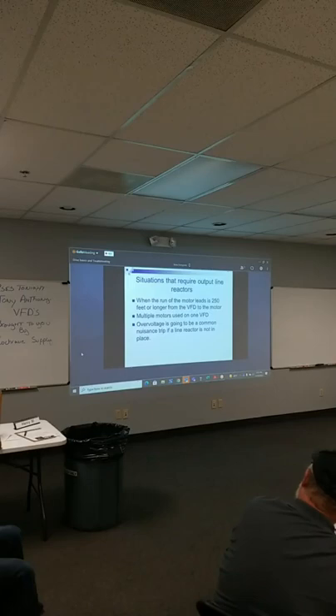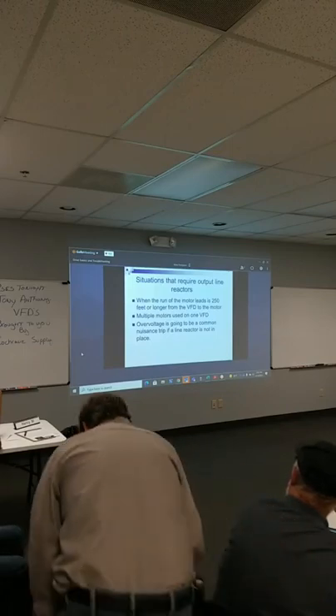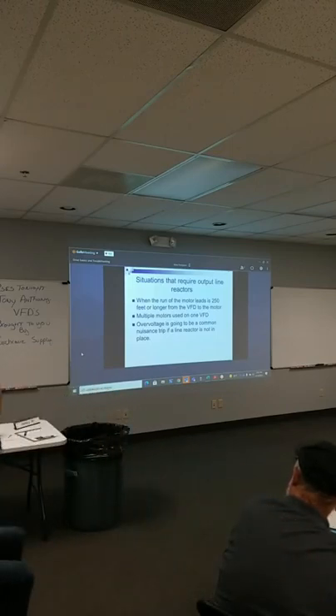Anytime your motor is more than a couple hundred foot from the drive, we need to think about this. Once again, remember I said you may have 1,000 volts if your motor's 5 foot from the drive. You take that exact same motor and run it out to 500 foot, you may see 1,600 volts at the motor, which generates more heat. So the rule of thumb is somewhere around, we say a couple hundred foot, this says 250. I've heard some manufacturers say 150. It really comes down to the quality of the motor.